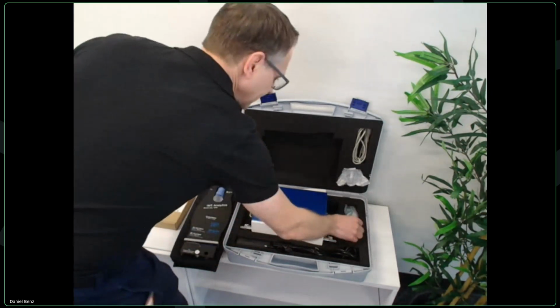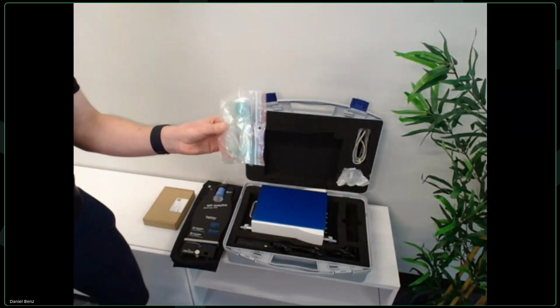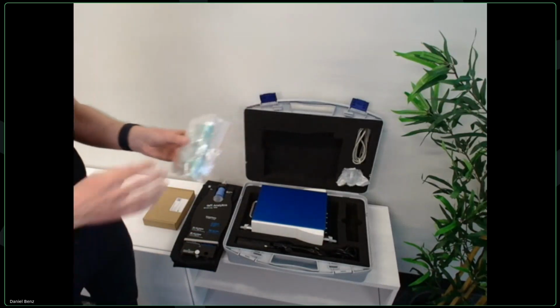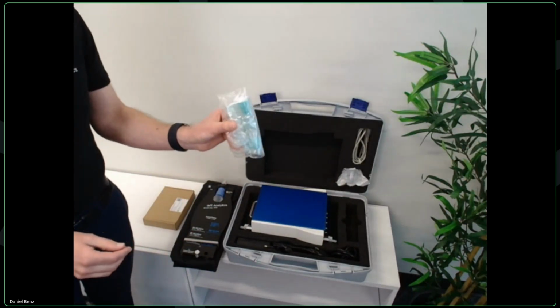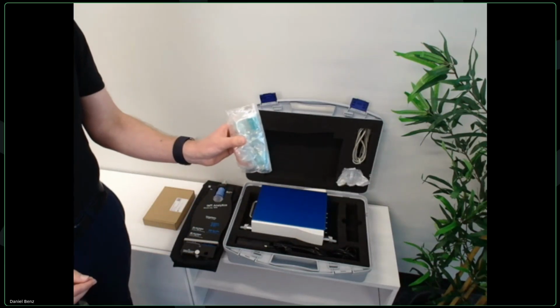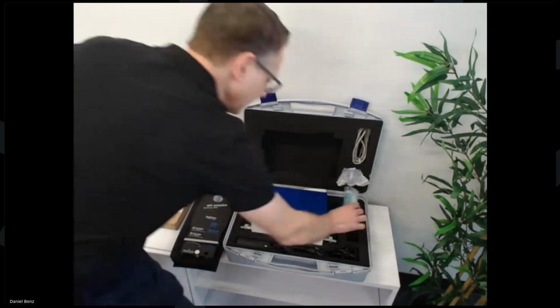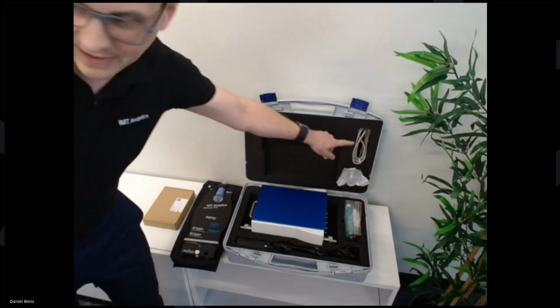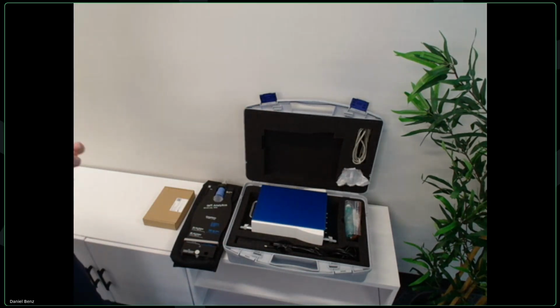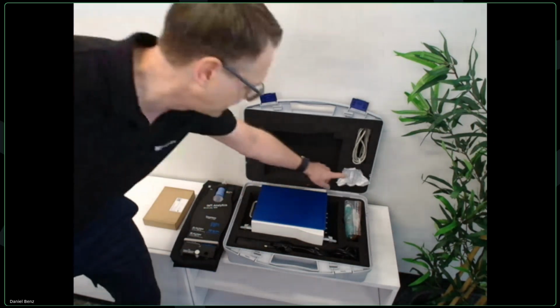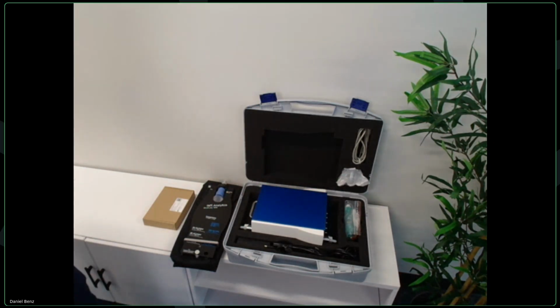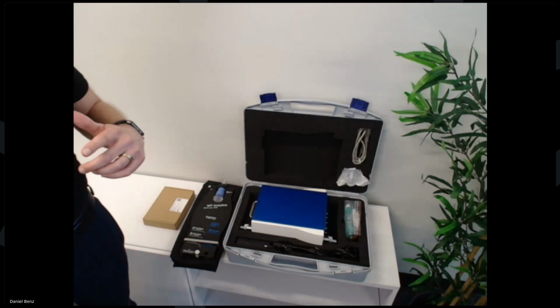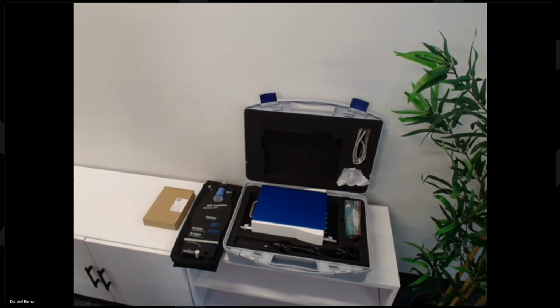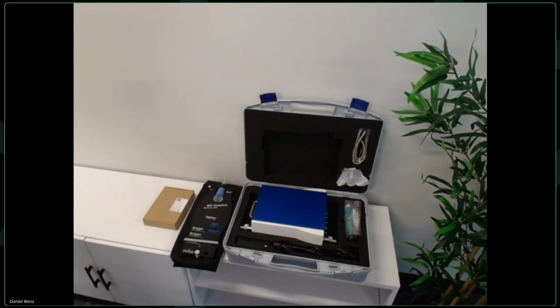Then we have an adapter set with all kinds of fittings you might need to connect your ventilator or whatever other medical device you're testing to our FlowAnalyser Pro. Then we have a USB cable up here, which is included to connect it to your computer. And we have a protection filter for the flow channel. We also offer it as a test set ventilation. We call that test set ventilation.